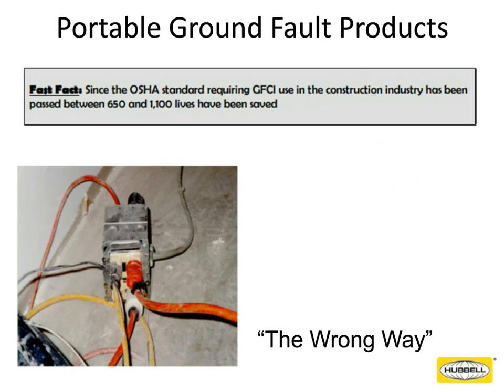What you don't want to do is make your own ground fault extension cords. This is a photograph that was taken at a facility very close to the Hubbell corporate office here in Shelton, Connecticut, where a contractor had basically made his own ground fault safety product. This does not meet OSHA standards for portable ground fault. Okay, so this has two ground fault receptacles. He's ganged up a couple steel boxes. He's put a cord connector on the end, and he's fed it, and he's using this to provide protection. It's probably better than no ground fault protection at all, but again, it does not meet the UL standard.